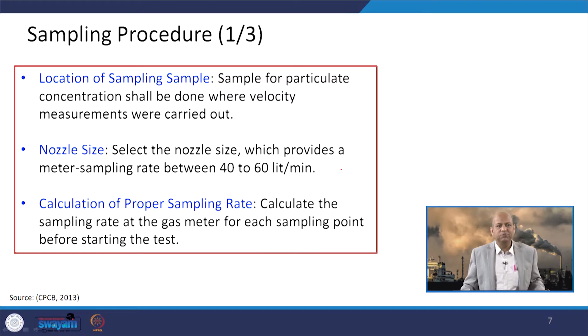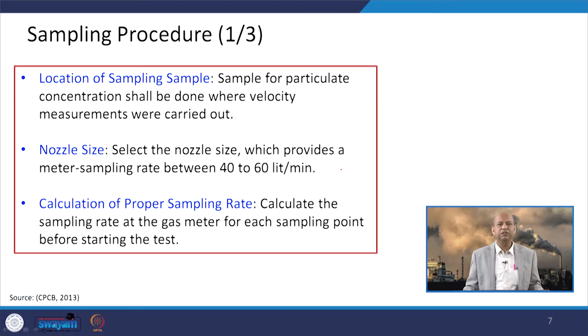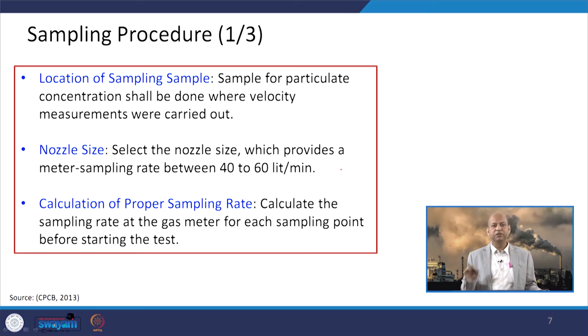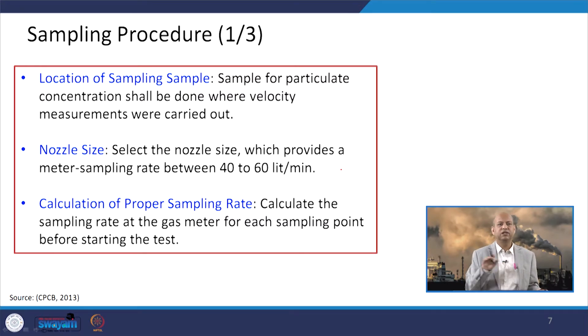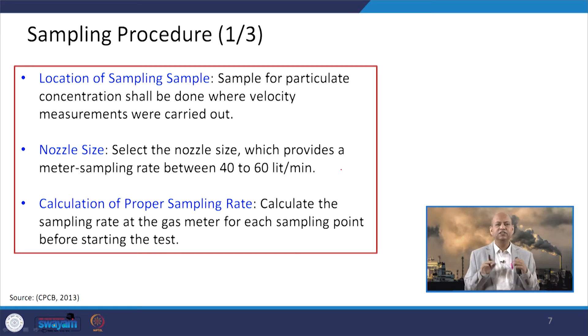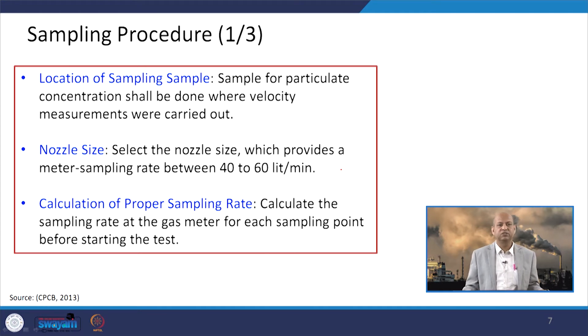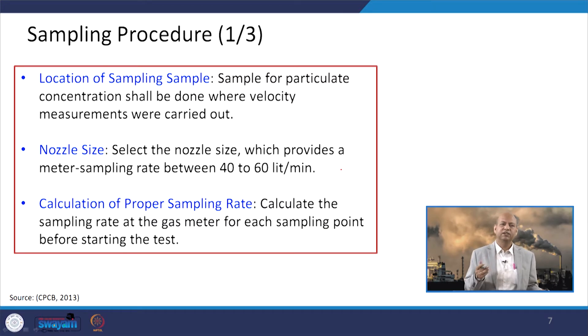There are important aspects regarding the location of sampling. The sample for particulate concentration shall be collected at the same point where velocity measurements were carried out — that particular point is very important. The nozzle size is selected so as to provide a metering sampling rate between 40 to 60 liters per minute, and that kind of nozzle size must be used.